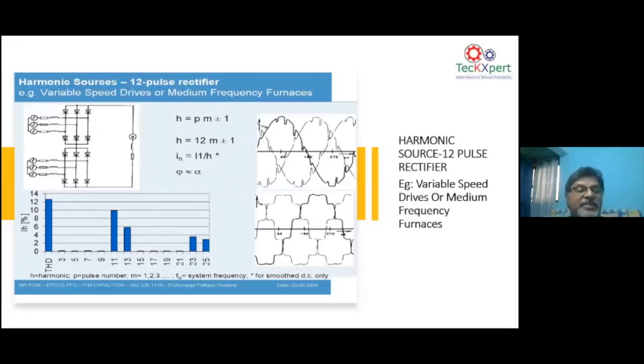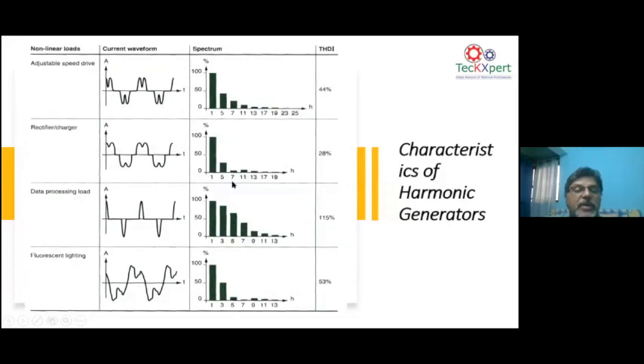As I told you, this is a 12 pulse. As you see, in a 12 pulse you don't have any other lower order harmonics. It only starts at 11 and 13 because of the equation 12 plus or minus 1.